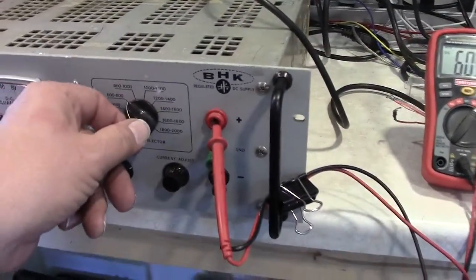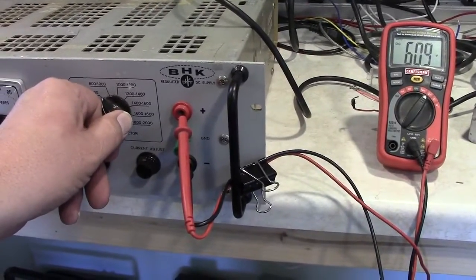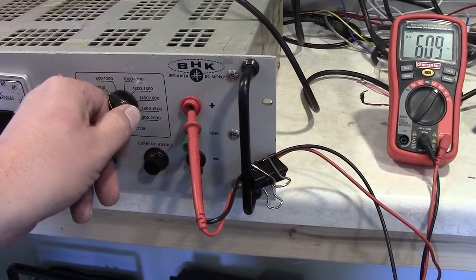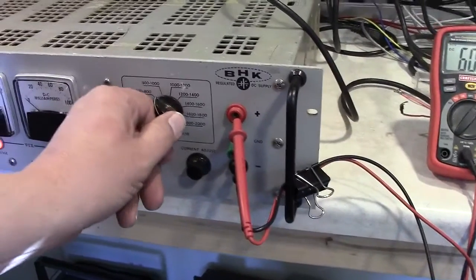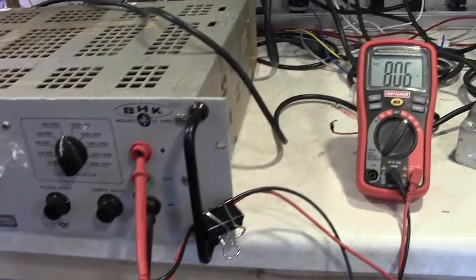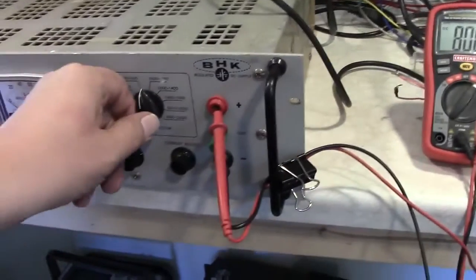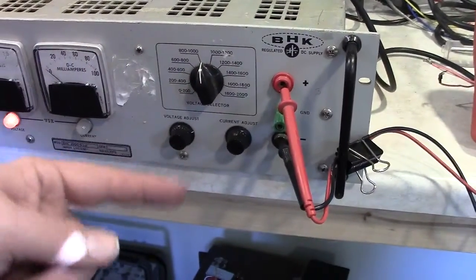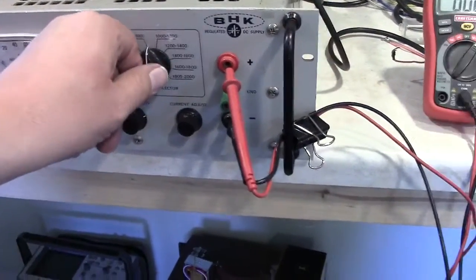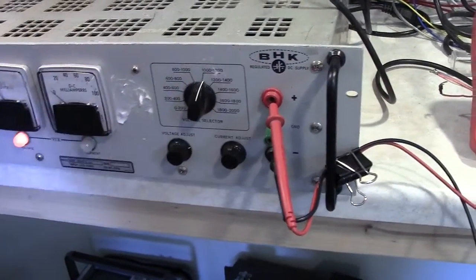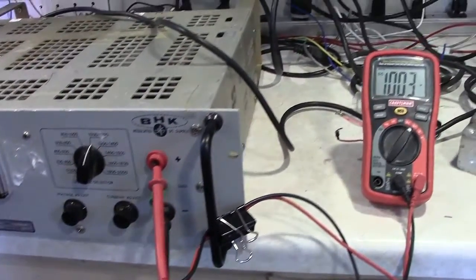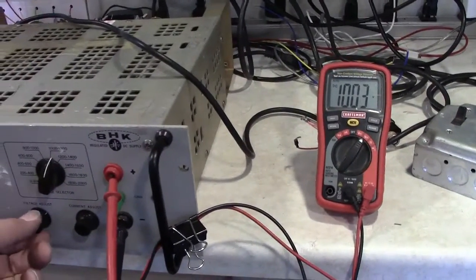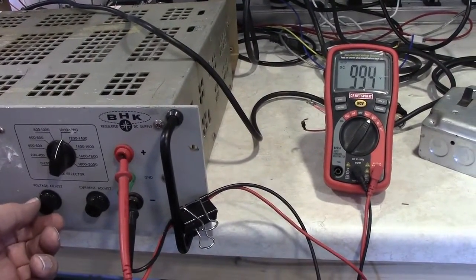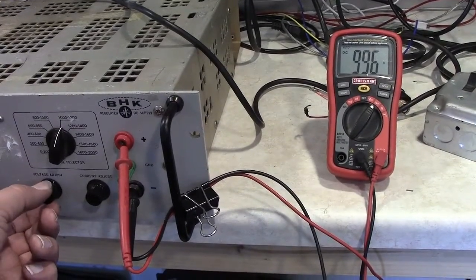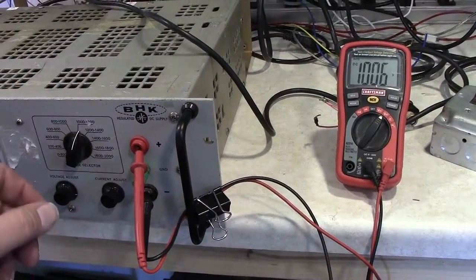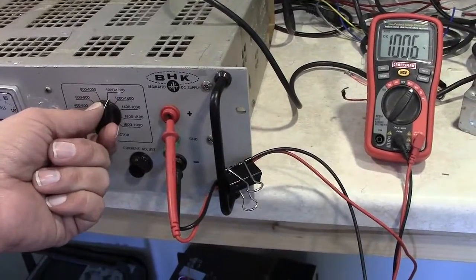We'll click it up to 1000. 1,000 volts. Oh wait, we've got to click it to the 800. And we go to 800 over there. Getting scary now because there's 800 volts on these wires. My meter beeps when it gets above 1,000 volts. Isn't that nice? Look at that. 994, no beep. Wow, look there. They're safety minded as well.